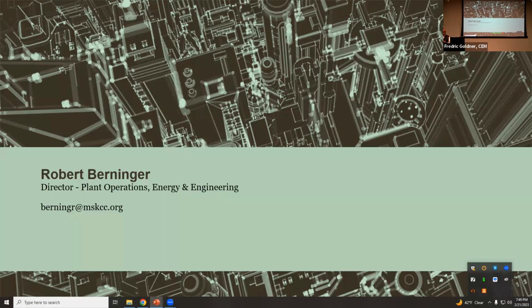Can I ask a follow-up? Yes. With all the electrification, you're at 180, slightly higher than what a heat pump does best. Correct. What's your opinion of further steps with electrification? You know, it's baby steps. When we started this project, talk of electrification was just beginning. MSK really was the last project that NYSERDA funded for cogeneration. All of a sudden, it was, oh yeah, we're not going to do cogeneration anymore. Gas is bad, cogen is bad. But in my opinion, switching to a hot water hydronic system gives us the possibility of the next step of matching the chilled water plant with the heating plant to do electrification.